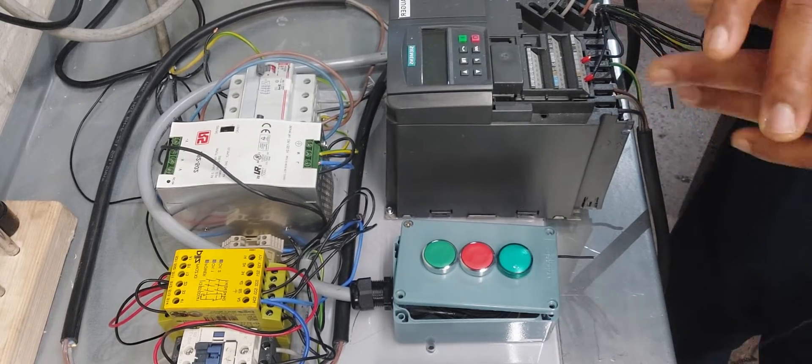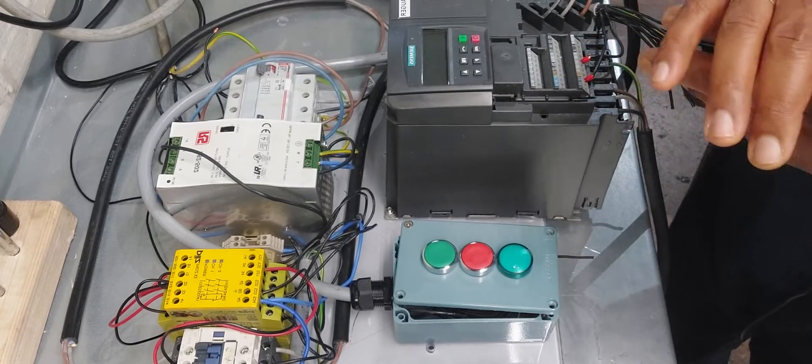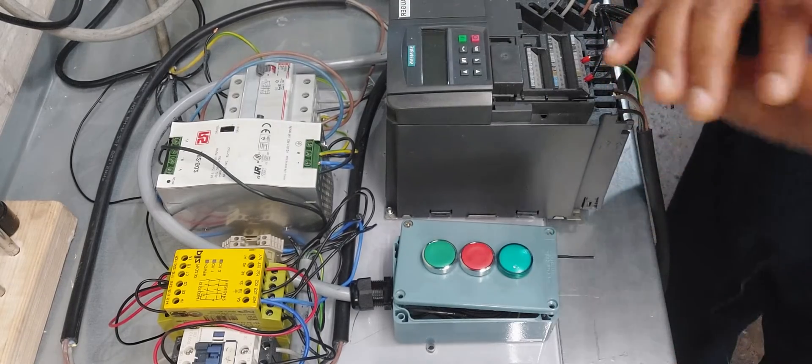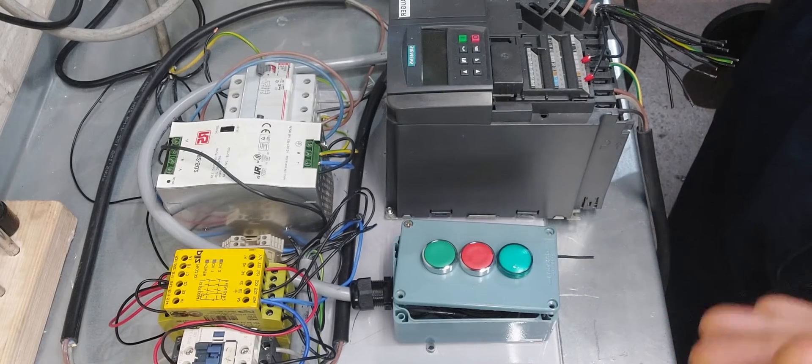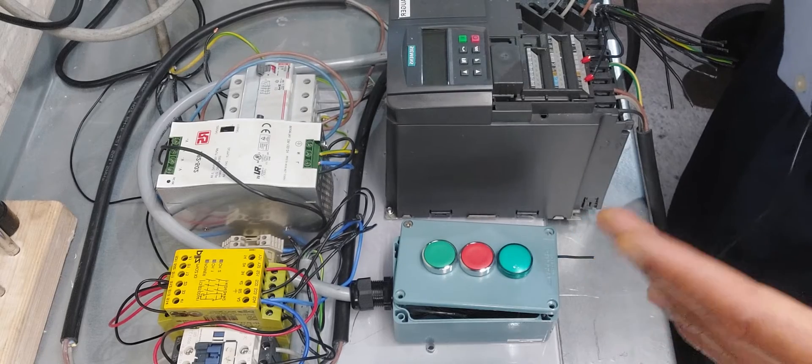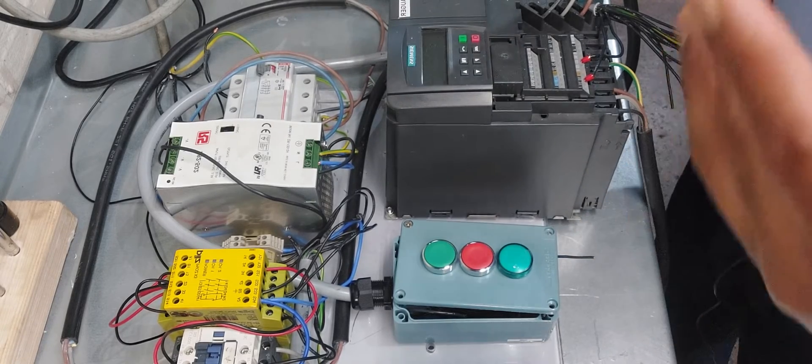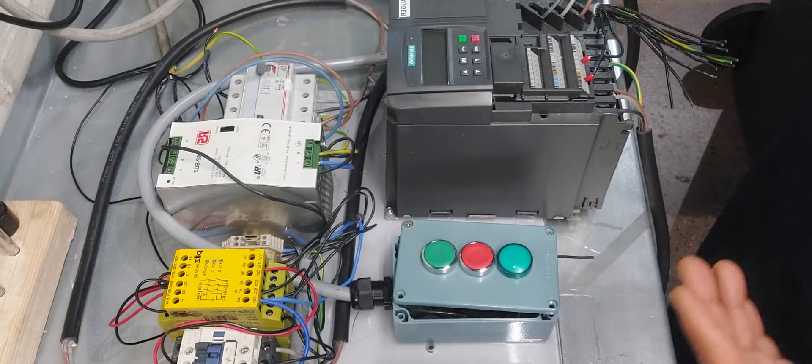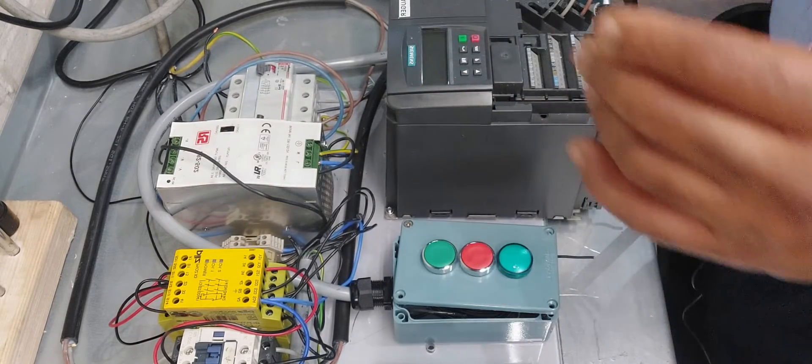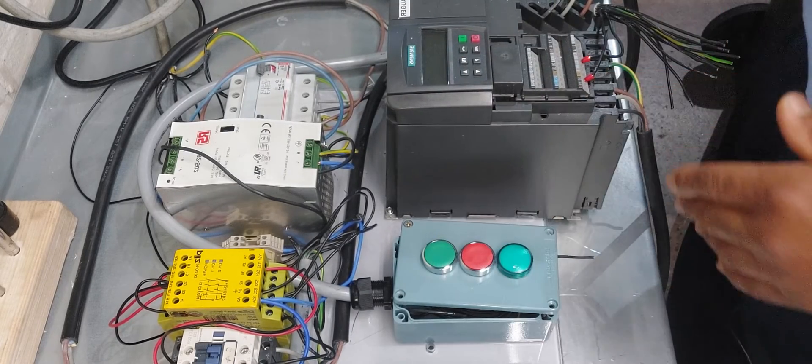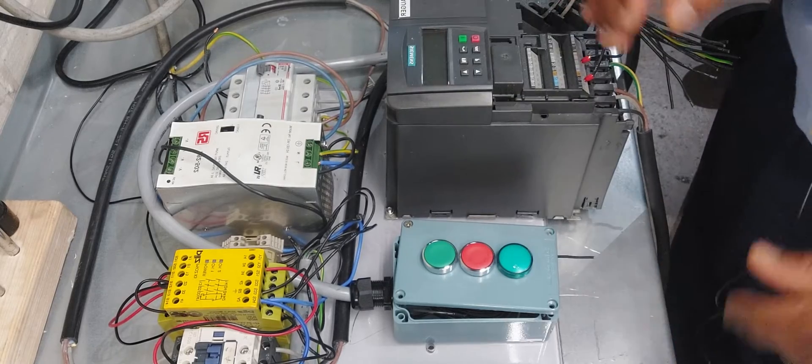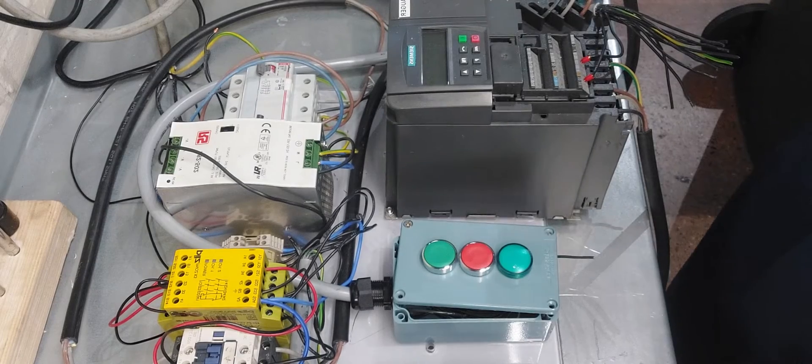We can use it to stop the machine if the process is going wrong, or if there's a part of the factory you don't want people to go into. You can put a light curtain—emitter and receiver sensors that emit infrared lights. Once these infrared lights are interrupted, it tells the Pilz X3 that somebody has broken the barrier. Switch off the whole machine until you reset it.